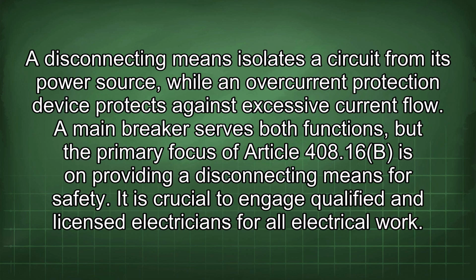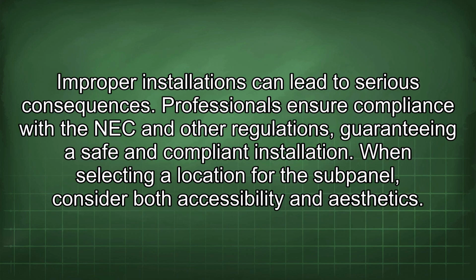A disconnecting means isolates a circuit from its power source, while an overcurrent protection device protects against excessive current flow. A main breaker serves both functions, but the primary focus of Article 408.16b is on providing a disconnecting means for safety. It is crucial to engage qualified and licensed electricians for all electrical work. Improper installations can lead to serious consequences. Professionals ensure compliance with the NEC and other regulations, guaranteeing a safe and compliant installation.